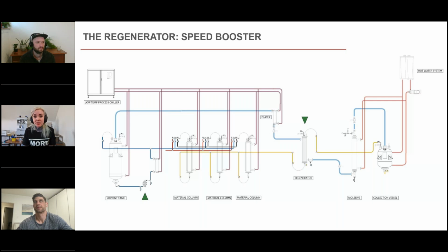A little bit of ice buildup in those coils won't stop your recovery - it just slows it down until the pump gets so hot it thaws it out backwards, and then it goes faster. So if your recovery seems faster at certain parts of the day, or certain staff seem faster at their recovery, you probably have old dirty water in your coils and need to thaw and blow them out. It clogs up easily, especially with particulate.